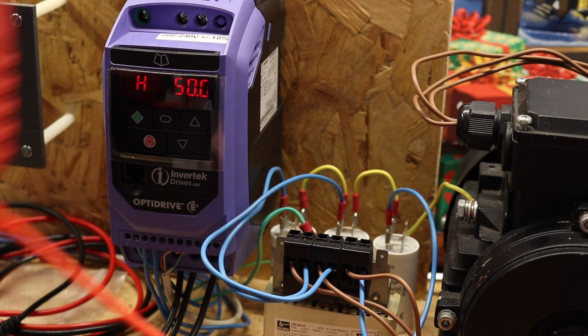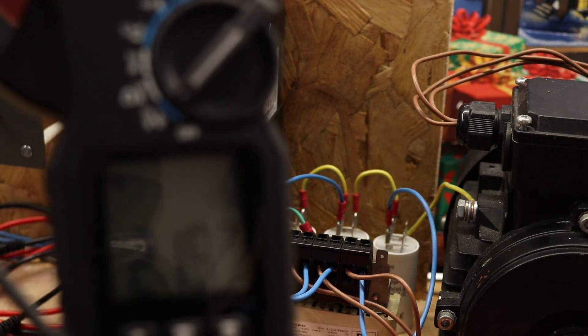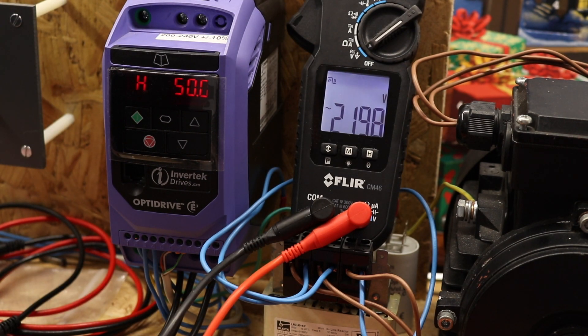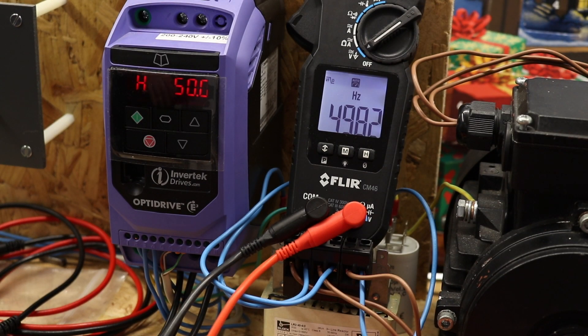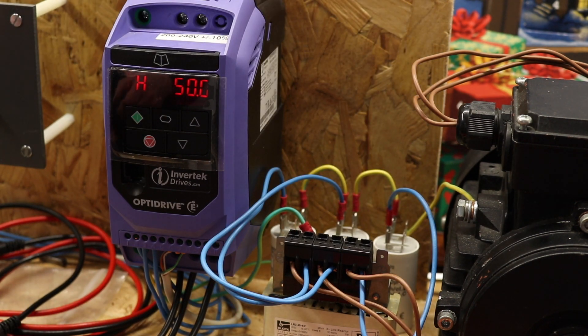The other clamp meter is the FLIR CM46. This one does have a VFD mode — you can see the VFD symbol in the top corner, and it appears to be permanently on for this one. It reads 219.7 volts — very good. Going to frequency, we've got 49.82 Hz — smack on, reading perfectly okay.